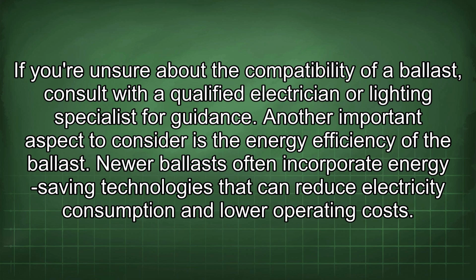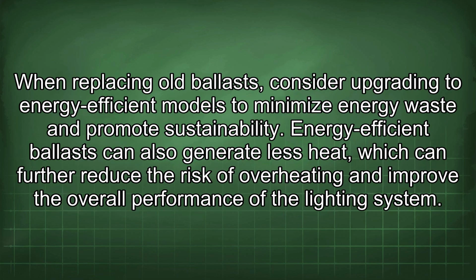Another important aspect to consider is the energy efficiency of the ballast. Newer ballasts often incorporate energy-saving technologies that can reduce electricity consumption and lower operating costs. When replacing old ballasts, consider upgrading to energy-efficient models to minimize energy waste and promote sustainability. Energy-efficient ballasts can also generate less heat, which can further reduce the risk of overheating and improve the overall performance of the lighting system.